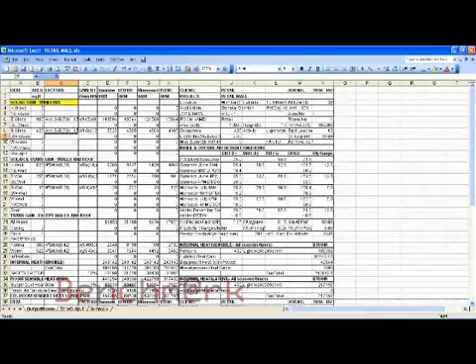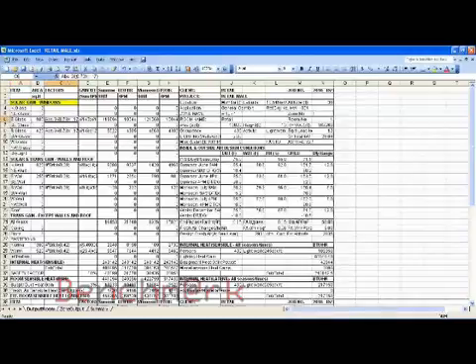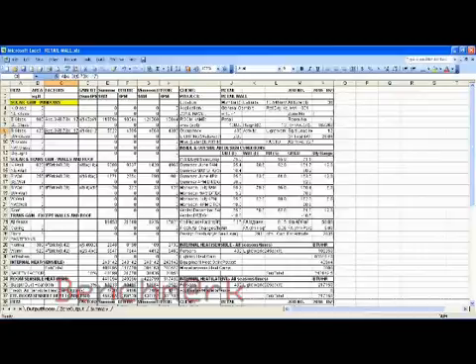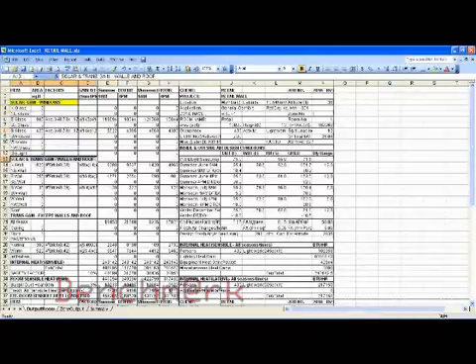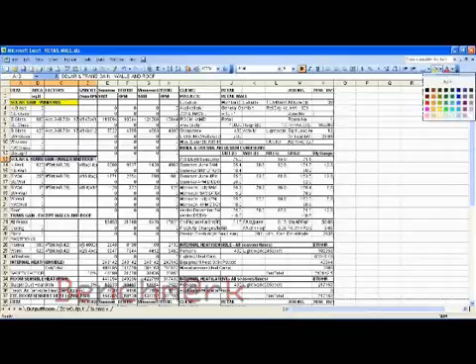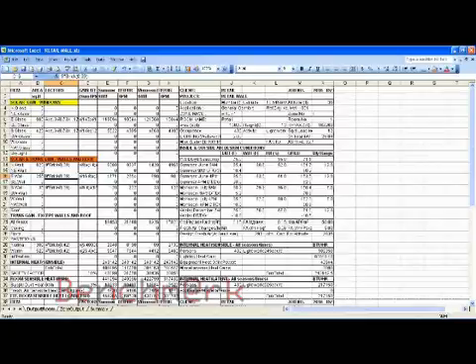This value is important to get the sensible heat factor. We get the sensible heat factor by dividing effective room sensible heat by effective room sensible heat plus effective room latent heat, and we indicate it with a chart. In this case we are selecting 50 degrees Fahrenheit for ADP.